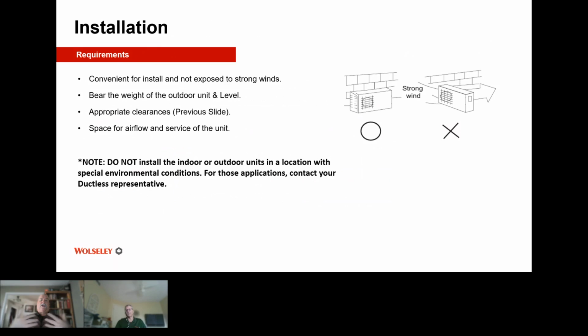So if you don't have an ideal location, I would recommend some sort of barrier, whether it's lattice or some sort of metal grating. You want to make sure that strong wind is not going to affect the performance of your outdoor units. Now, I know that strong winds won't sit there and turn an outdoor blade assembly on its own. If that is happening, we have another problem besides the strong wind. There's something wrong with our fan motor itself. But generally, we want to protect the outdoor unit from direct strong winds, okay?